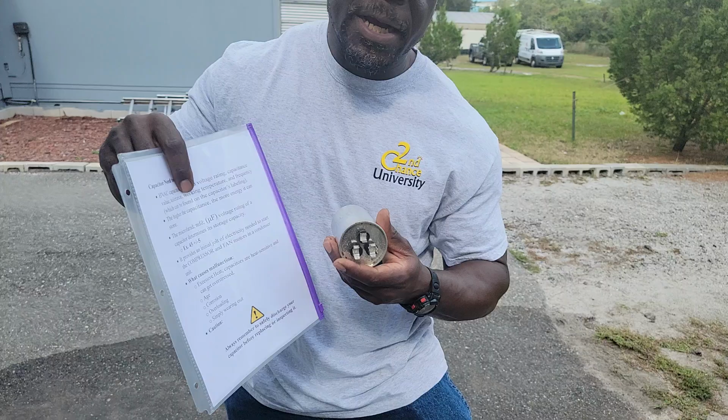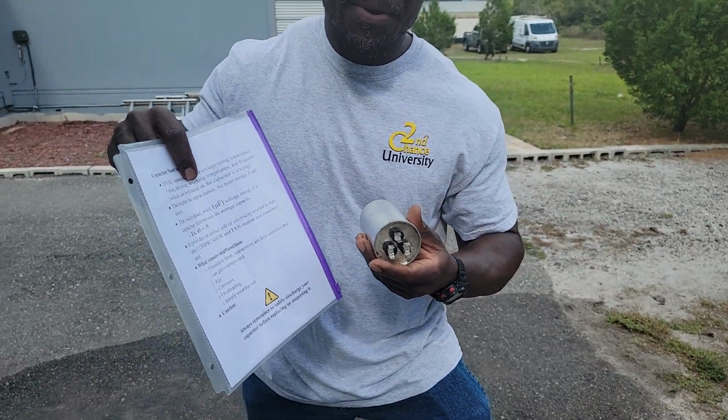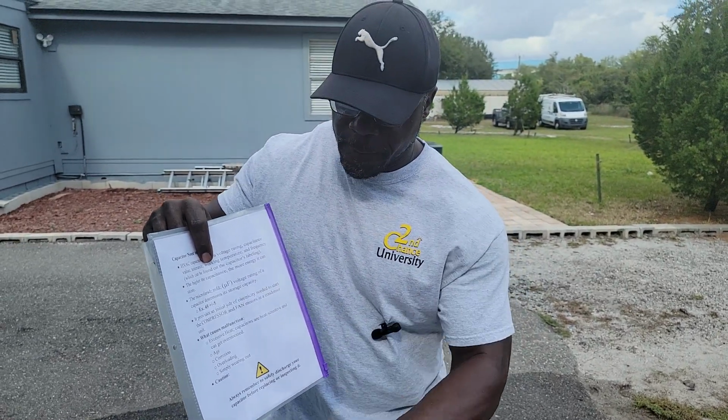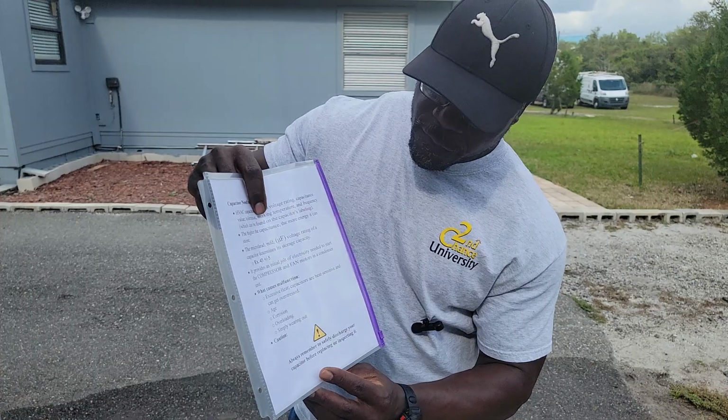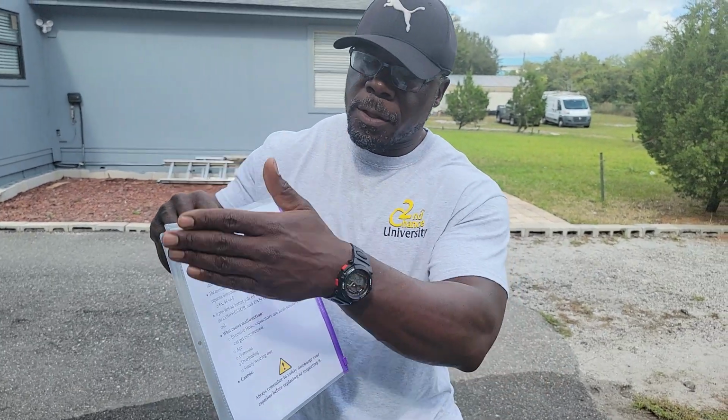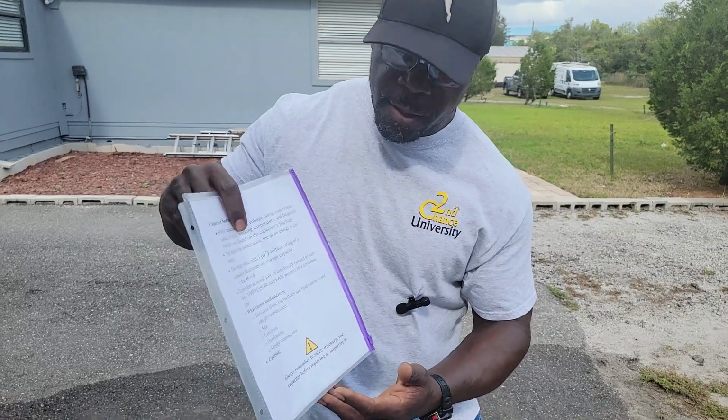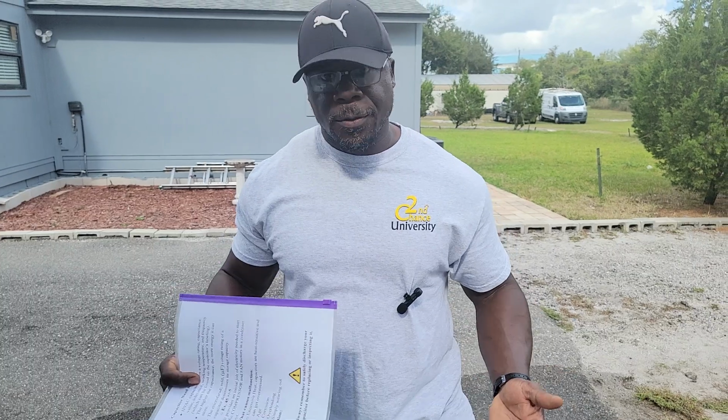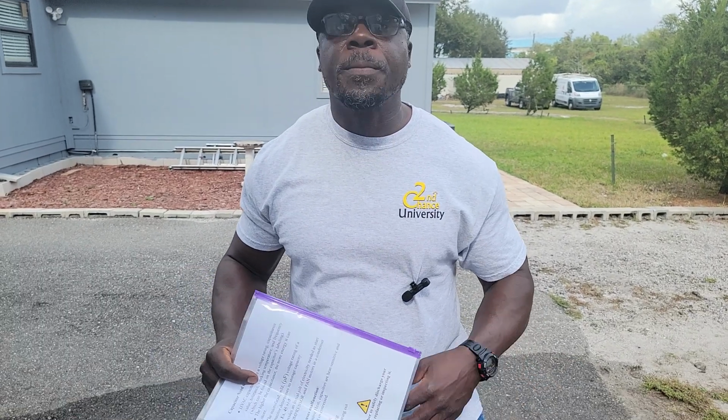Corrosion: if this area right here gets corroded, it will ruin the connection, and then you won't be able to get the full charge that you're going to need. Overloading, from an electrical strike or something going wrong with your power source coming in, can damage it as well. And simply wearing out. Some things just age out. Capacitors do the same, like any other replaceable component in your condenser unit.